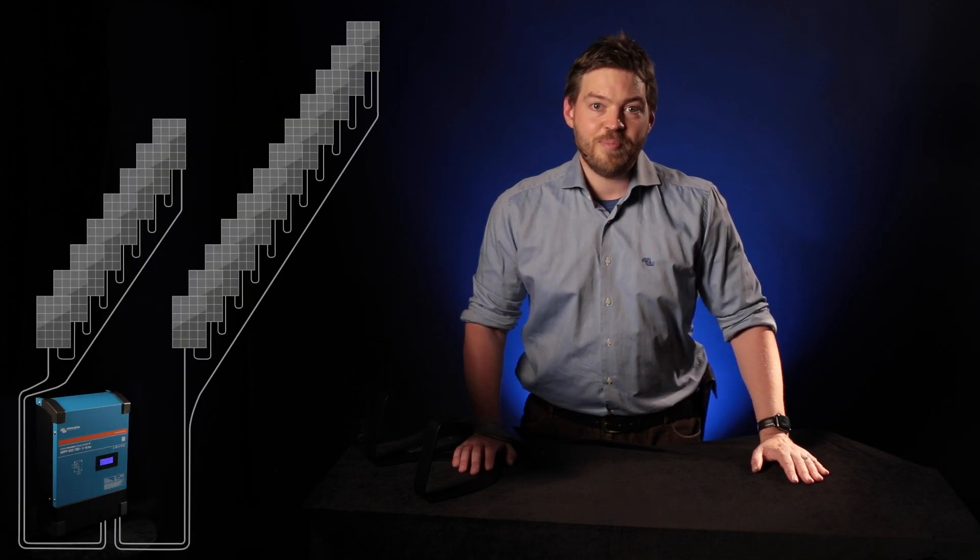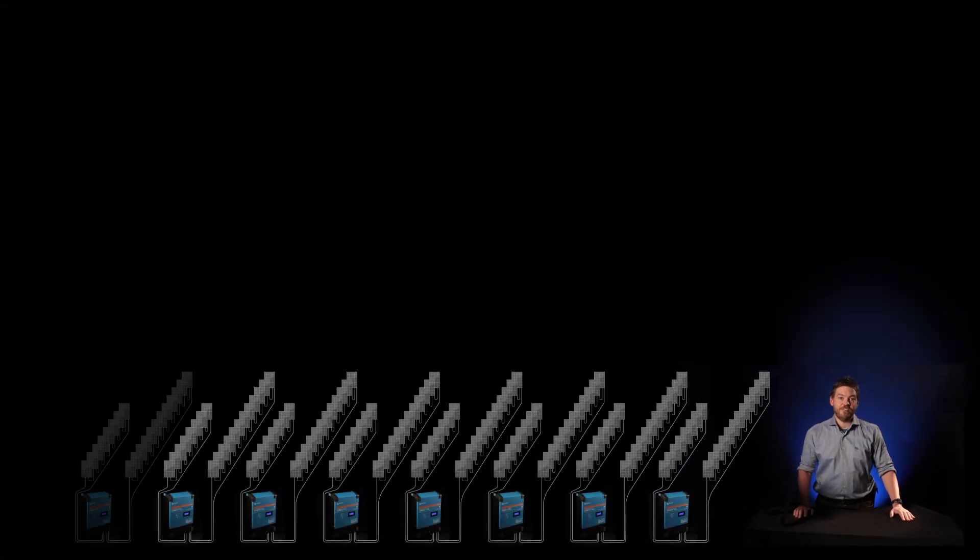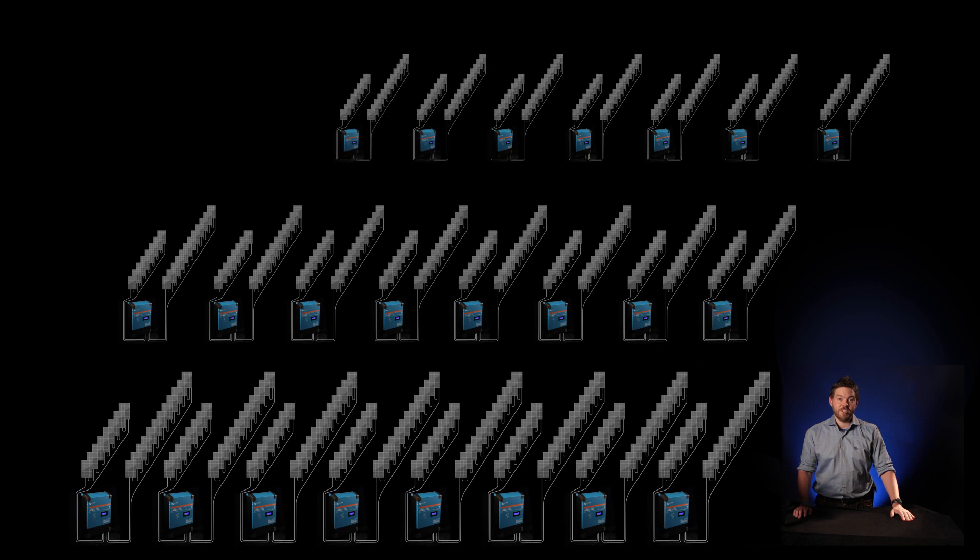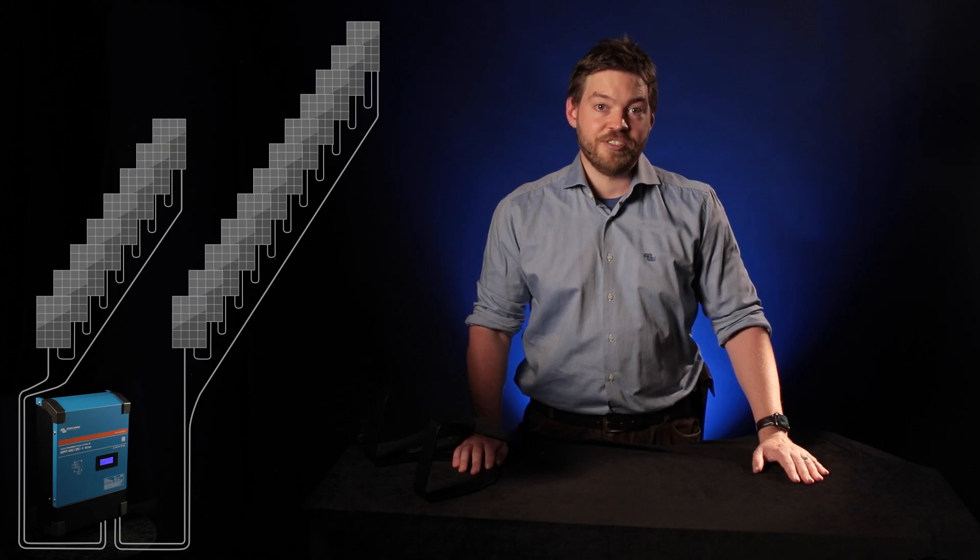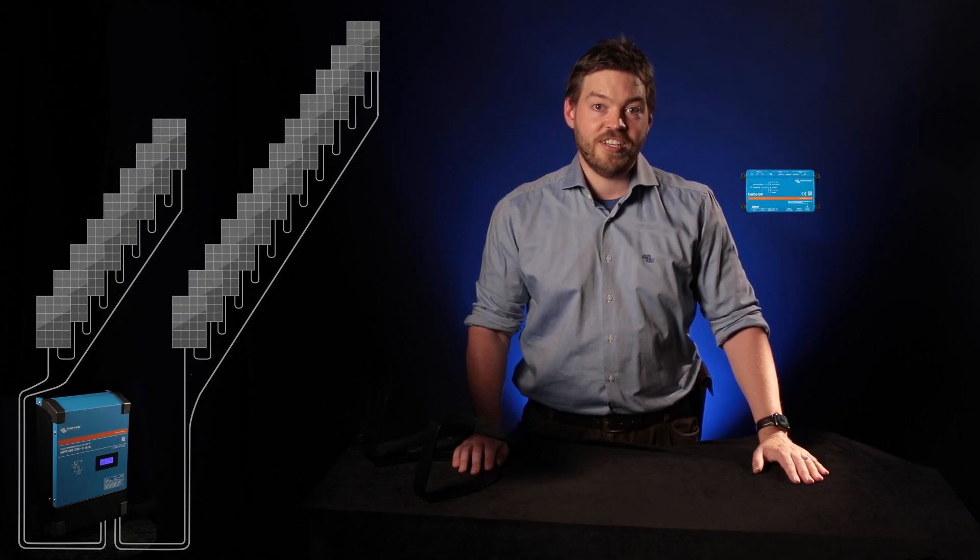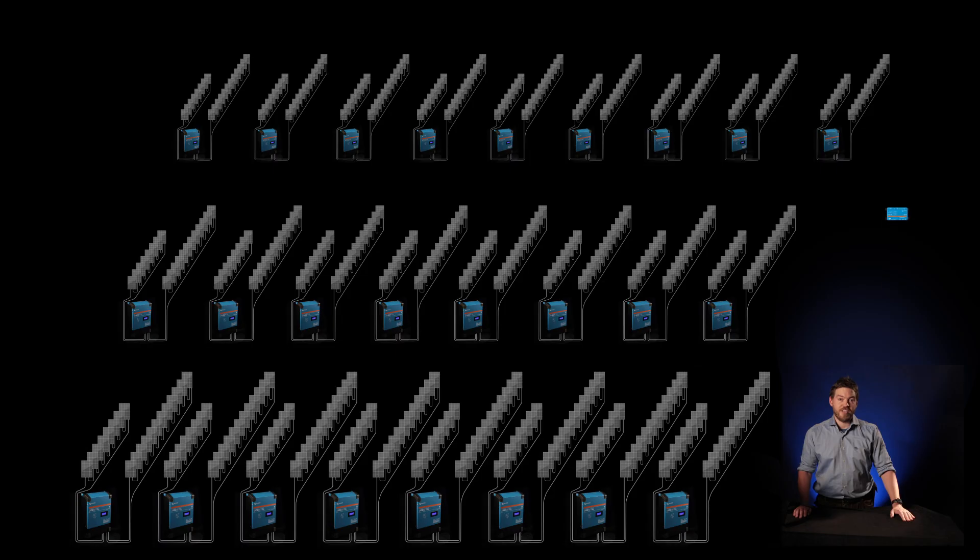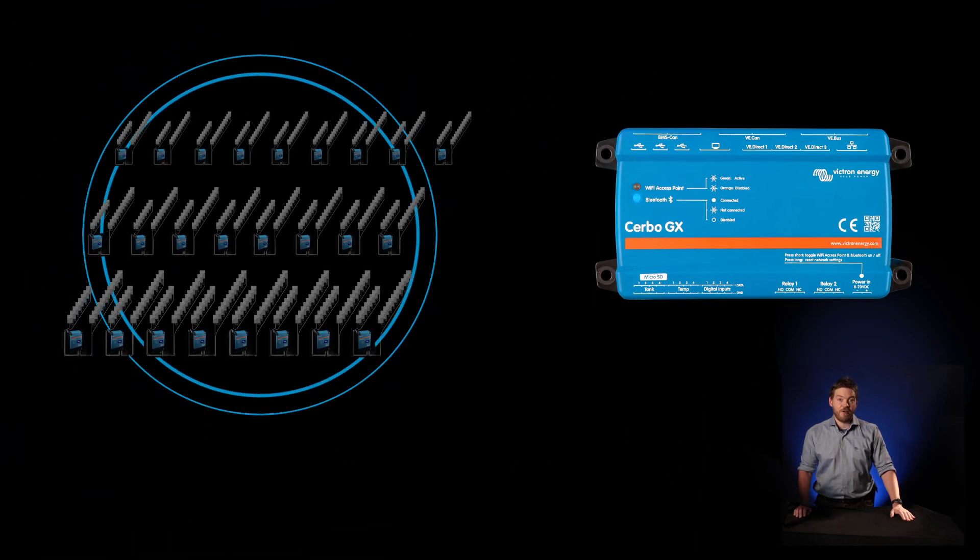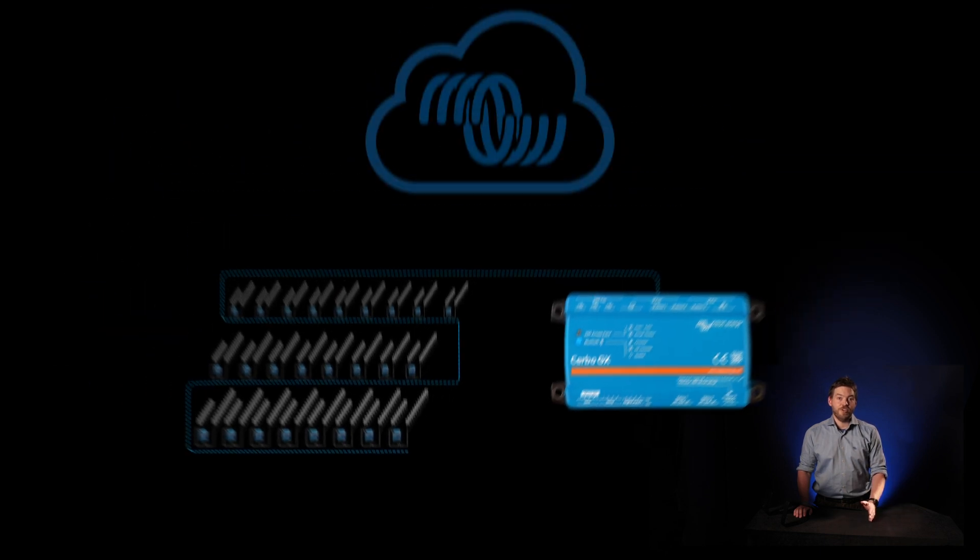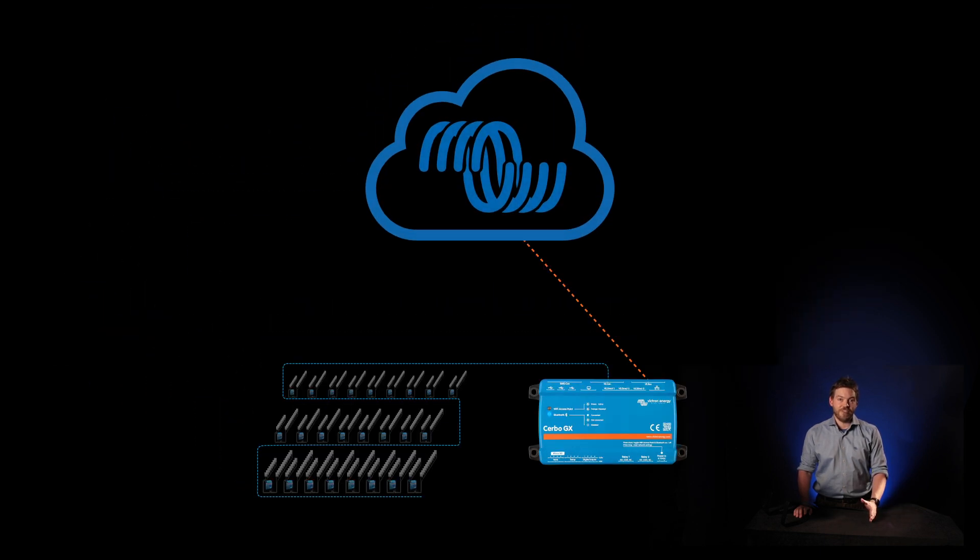The MPPT RS has all the usual Victron connectivity options. It's a smart unit so it comes with built-in Bluetooth. This means you can connect using the Victron Connect app. It also contains VE.Can ports. These VE.Can ports allow you to connect up to 25 units in parallel and have them synchronize. You can also connect these into a GX device to take those 25 MPPTs up to 125 kilowatts of power and communicate all that through to the Victron remote management portal VRM.